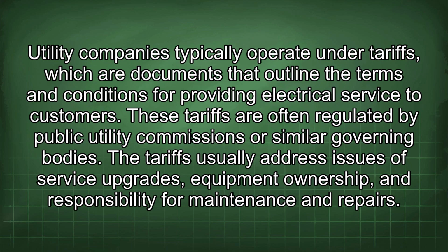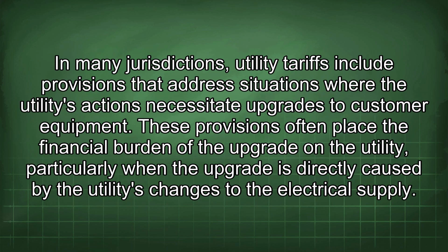Utility companies typically operate under tariffs, which are documents that outline the terms and conditions for providing electrical service to customers. These tariffs are often regulated by public utility commissions or similar governing bodies. The tariffs usually address issues of service upgrades, equipment ownership, and responsibility for maintenance and repairs. In many jurisdictions, utility tariffs include provisions that address situations where the utility's actions necessitate upgrades to customer equipment. These provisions often place the financial burden of the upgrade on the utility, particularly when the upgrade is directly caused by the utility's changes to the electrical supply.